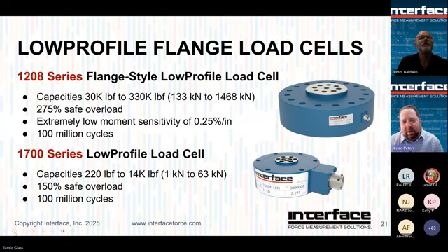1700 is a similar model, with a much more unique and specific flange pattern to accommodate very industry standard bolt patterns on the actuators. So again, in Europe and other places, actuators come with different mating surfaces, and we have solutions to mate up with them. And again, because they're going to be tied to actuators, most of the time you're doing cycle testing, right? So it makes sense that these are fatigue rated. Next slide.